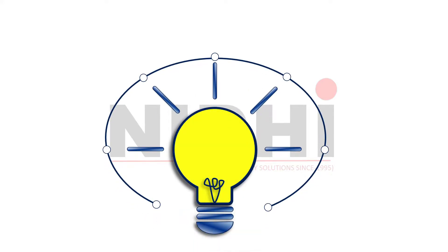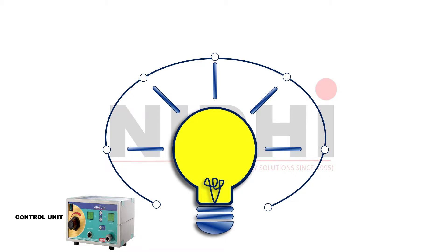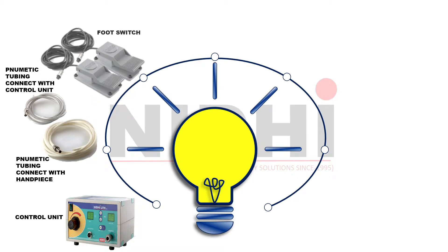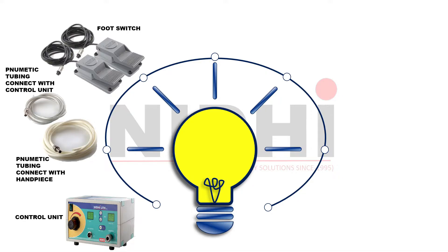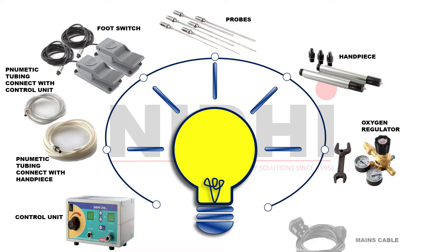Let's take a brief look at what instruments we are getting in the Nidhi Lite Digital Kit. First of all, we are getting the Nidhi Lite Digital Control Unit. Along with it, we have two types of tubing. We have also received two foot switches, but we need only one at a time to operate Nidhi Lite Digital effectively. Then we have six probes of different sizes. We have received two hand pieces — we need only one at a time, the other is a spare. And we have an oxygen regulator and mains cable in our kit.